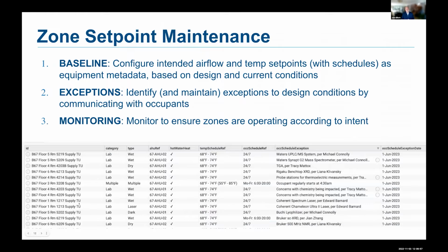We're also doing some of this work at the zone. So this is a lot of detailed work. A lot of it has a few different elements. So one is just what is the intended operation of the zone? So establishing a baseline. So we're identifying the intended airflow and temperature set points along with the schedules, and we're placing them in SkySpark as equipment metadata. So this is kind of a research exercise. We're going back to the original plans for the project, understanding the original design intent, and then updating that with current conditions. It's often, I think, not generally known what the expected operation of the building is, and we're trying to establish that and bring it into our systems.